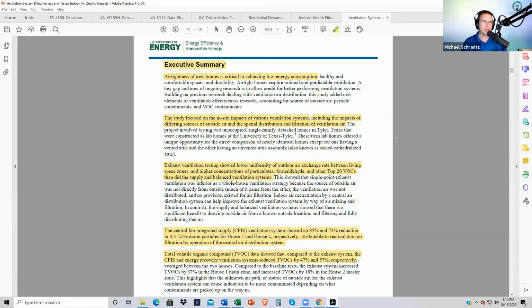And I think the irony of it is that most homes - a strong wind from outside will depressurize or pressurize the home depending on the nature. Meanwhile, you're using that 200 CFM kitchen hood exhaust that's pulling out. In most homes, the builders - I was lucky to work with a couple of them - but most didn't even have intentional makeup air for those hoods. And so there's intermittent use of exhaust fans.